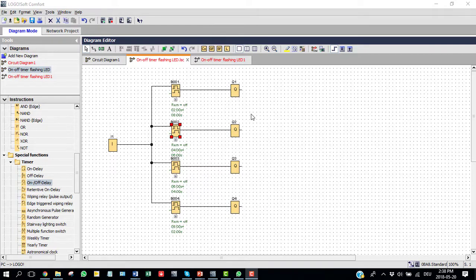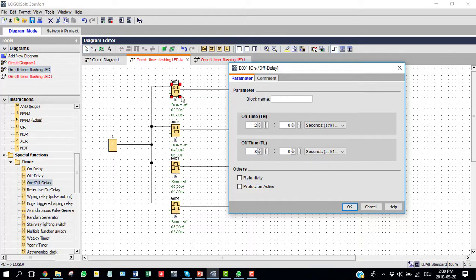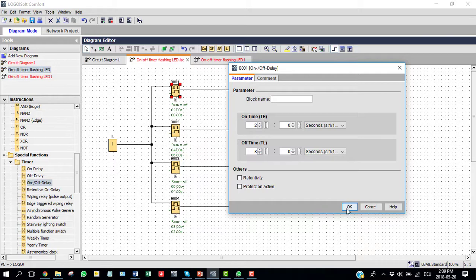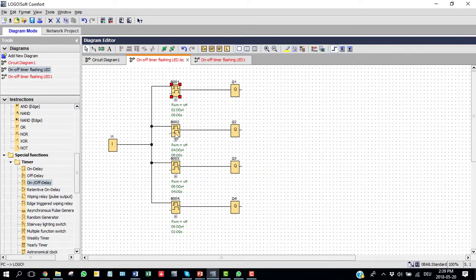And in parallel, I took four on off delay timers just to control the loads sequentially. If you press on off delay timer, the first one, you see here on time is two seconds and off time is eight seconds, because I want to control sequentially on off forward and reverse direction.